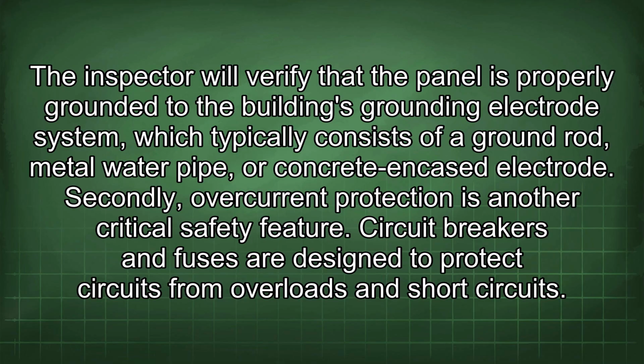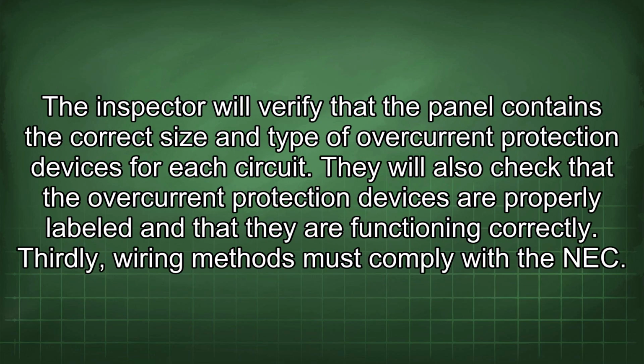Secondly, overcurrent protection is another critical safety feature. Circuit breakers and fuses are designed to protect circuits from overloads and short circuits. The inspector will verify that the panel contains the correct size and type of overcurrent protection devices for each circuit. They will also check that the overcurrent protection devices are properly labeled and that they are functioning correctly.